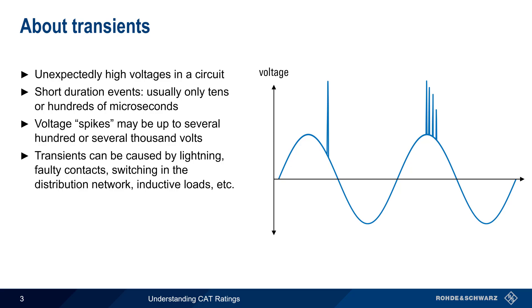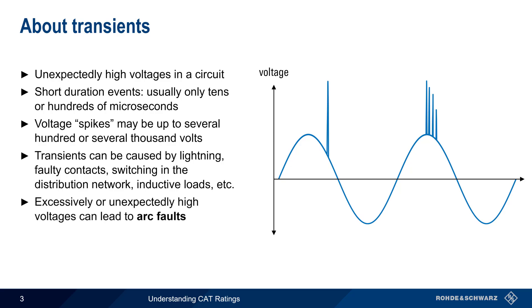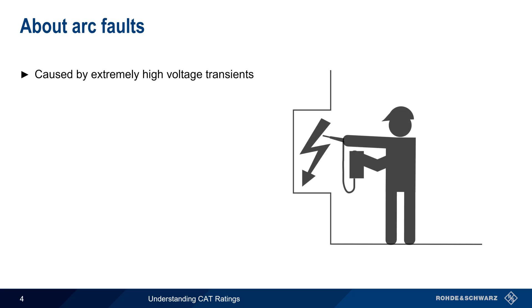Although very high voltages are dangerous in and of themselves, transients can also lead to an even more dangerous condition, namely arc faults. Arc faults, also called arc flashes or arc blasts, can be caused by extremely high voltage transients, and the higher the voltages, the greater the risk of an arc fault.